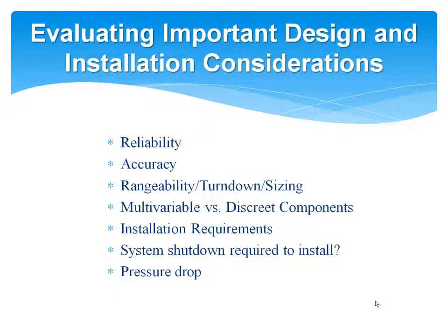I'd like to run through here some very important installation and design considerations for steam flow measurement. These are really in kind of a prioritized order, although that order may change based on application. For example, if you're going into an existing system and you can't shut the steam line down, well, that second to last bullet all of a sudden becomes quite a bit more important and maybe moves up the list. But again, we'll run through these individually quickly here.